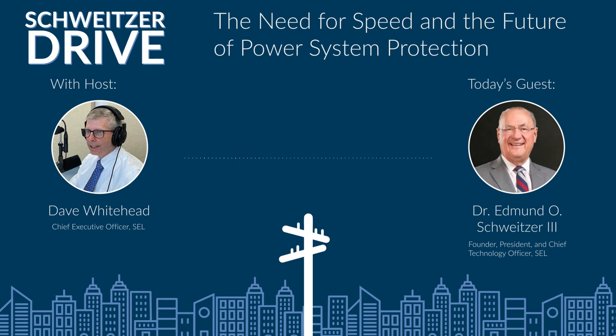But there are other good things about this traveling wave protection, time domain protection, because we can figure out where the fault is quicker than anybody else can trip for that fault. So we not only trip, and while the breaker's lumbering along there, trying to get its mechanism unrolled and open its contacts and wait for a current zero, we already know that the fault is 18.235 miles down the transmission line, and then the relay can think ahead and say, wow, that's in a chunk of cable, not an overhead line. We better not reclose for that one. We can get that all figured out before anybody else is able to trip the breaker in the first place. So the speed not only benefits the fault clearing time, but the fault locating is also doggone fast, so that we can use it in control schemes such as reclosing.